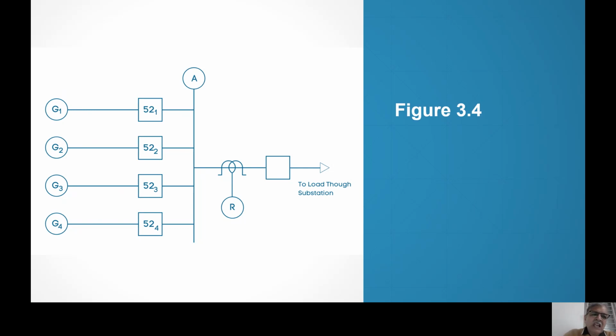One has to appreciate and understand that if G1, G2, G3, G4 are thermal power plants, you cannot make them off and on like a switch. It is not possible. But if you've got gas turbine plants, combined cycle power plants, diesel power plants, or even hydropower plants, you can. Hydropower plant starting time is about half an hour. Thermal power plant starting time is 7 hours. You cannot make it on and off like a switch, but other plants you can make off.